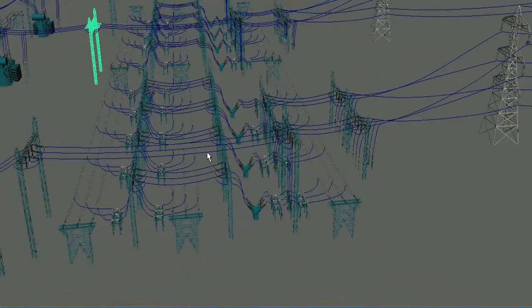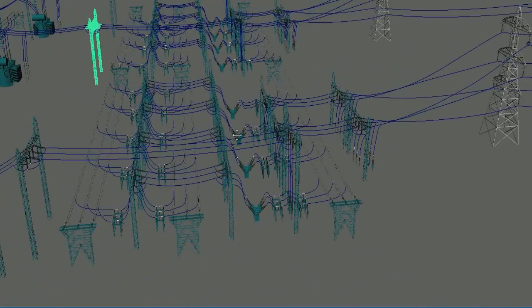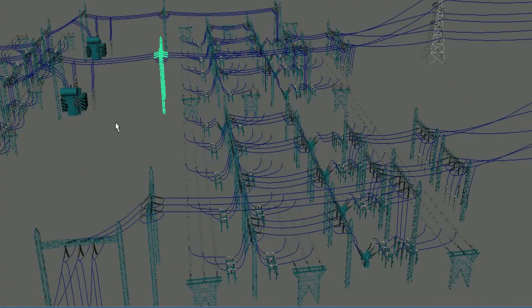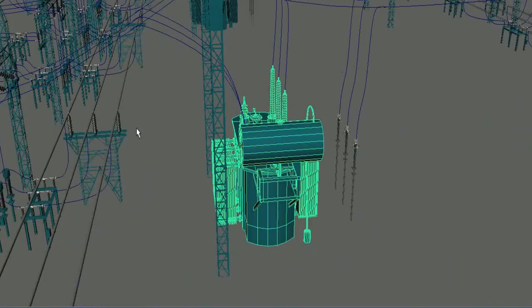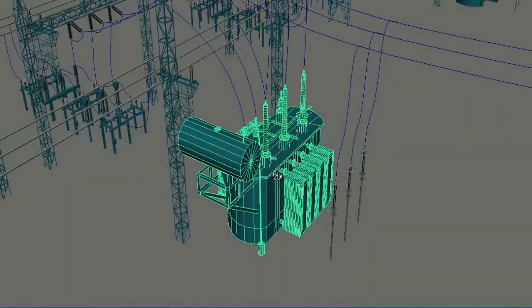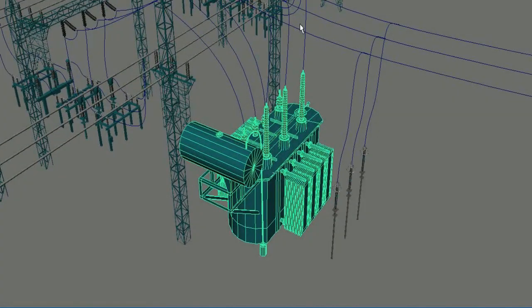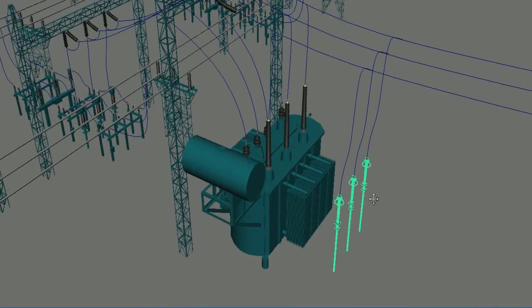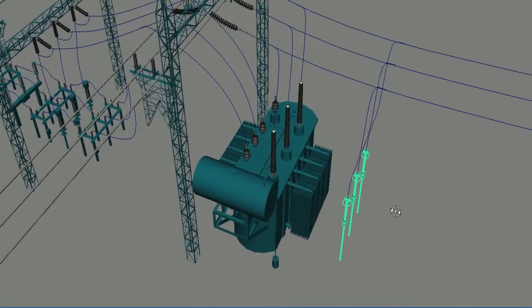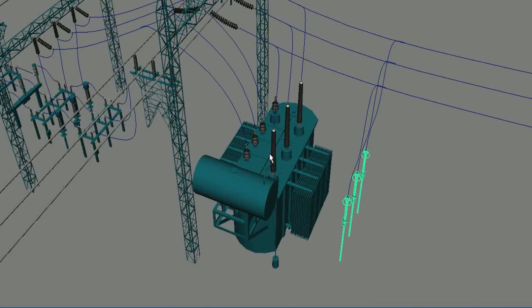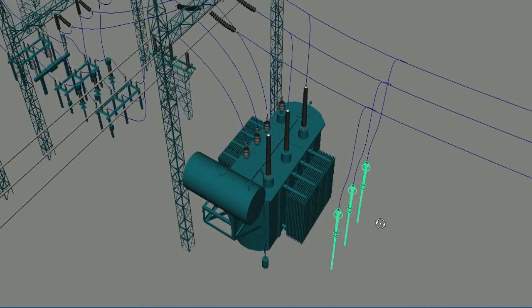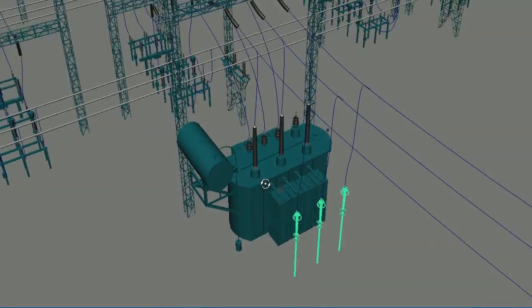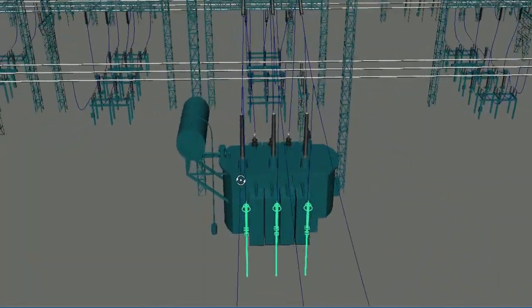Voltage spikes must not enter into sensitive devices like transformers, otherwise they could cause damage to the winding insulation and may cause dangerous accidents. Therefore, surge arresters are installed just before its terminal, and this arrangement is not only done for transformers, this is done for every kind of important equipment like generators.